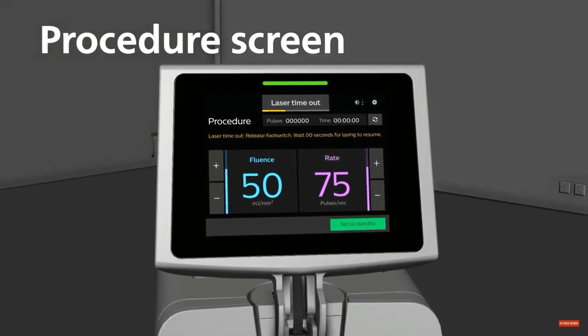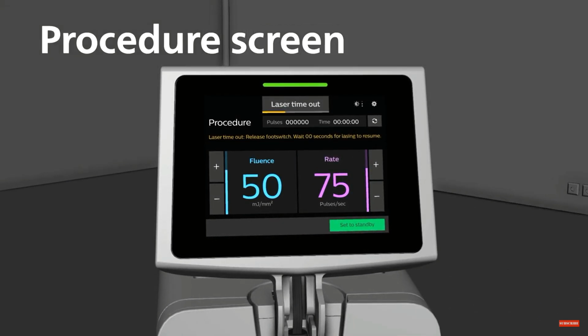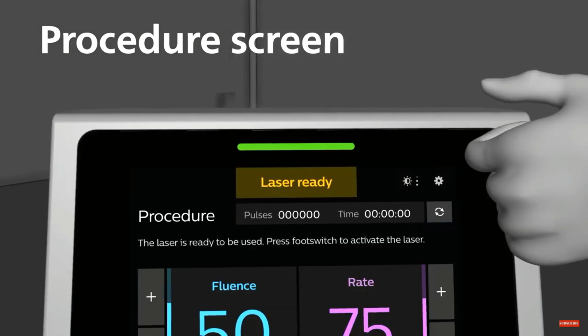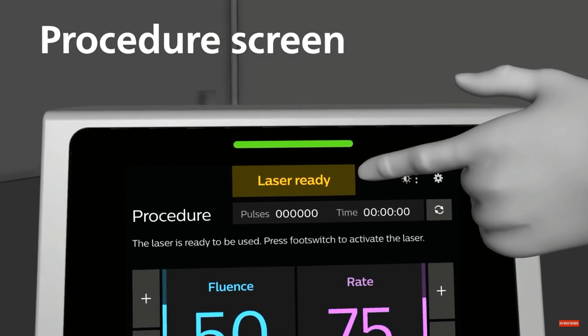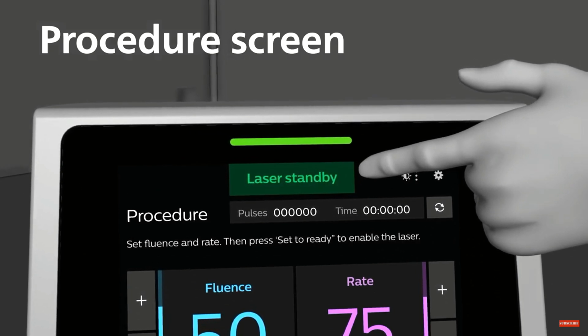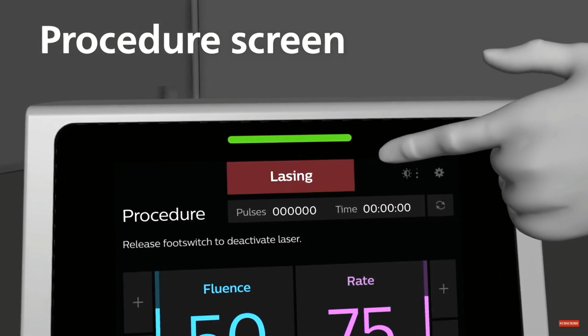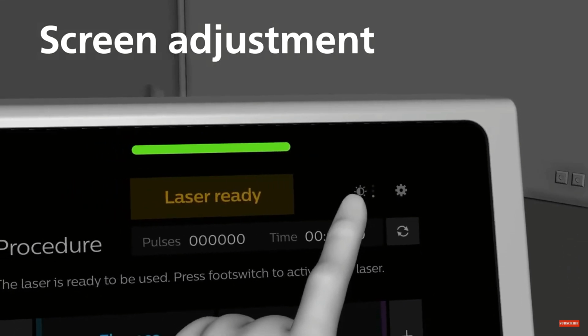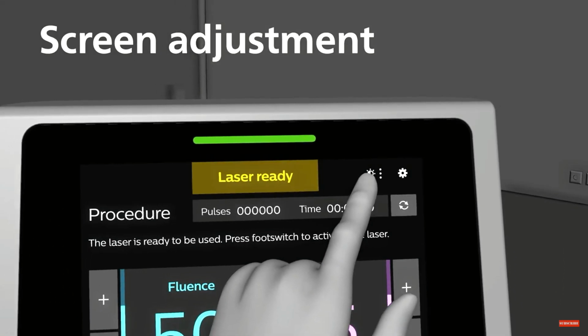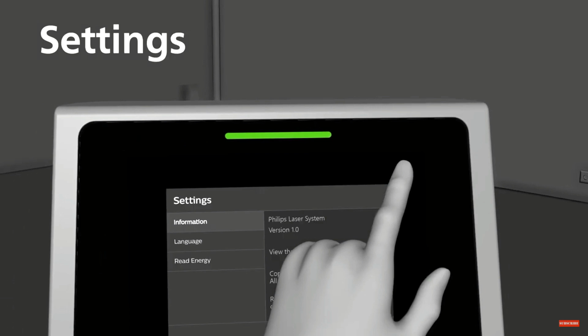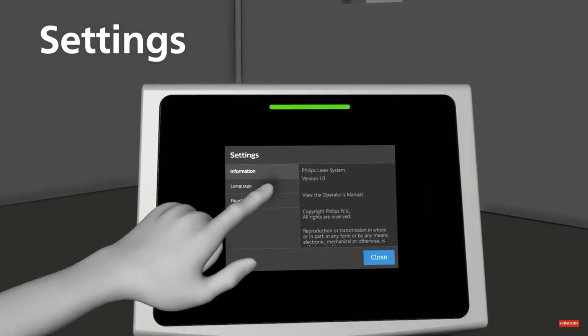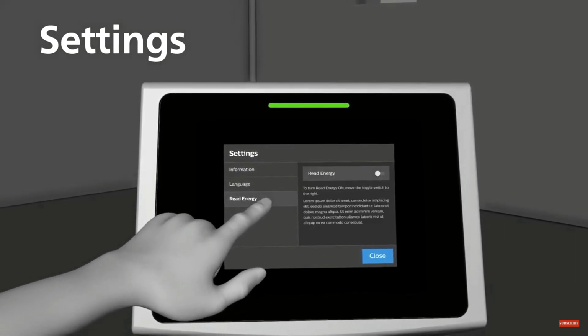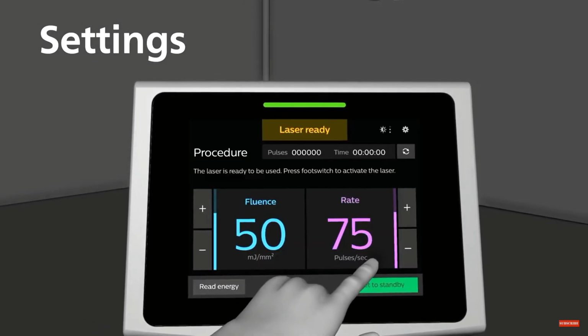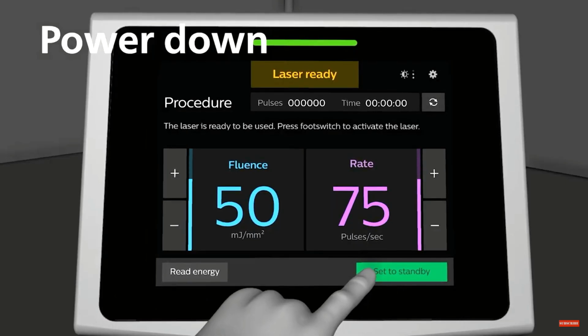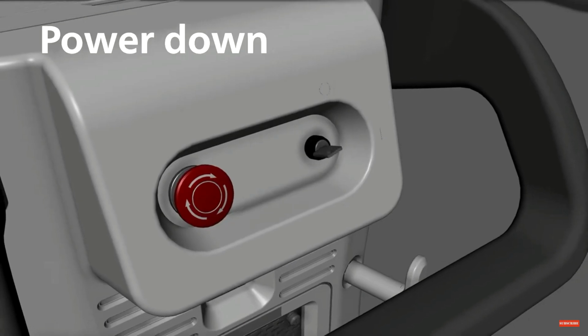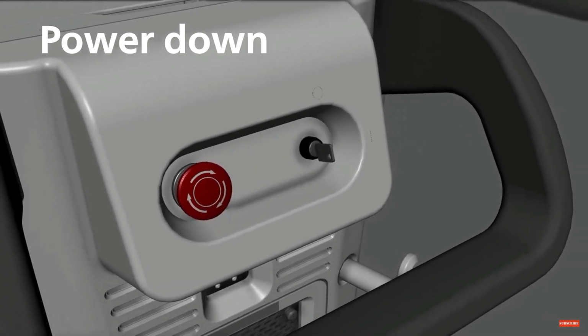There are color-coded screen advisories, indicators, and status information for ease of use. Yellow when in ready mode, green when in standby mode, and red when the system is lasing. The screen brightness can be adjusted to one of 3 preset brightness levels. The settings menu provides information about the system, allows the user to change language, and turns on the read energy function. To power down the system, press the standby button and turn the key switch to the off position.